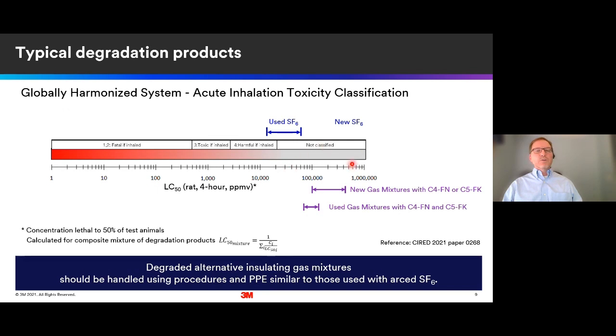Try to put those into perspective. If we look at where those mixtures fall, again, on that GHS, the Globally Harmonized System scale, in this case, it uses the acute inhalation toxicity classification. It's based upon the 4-hour LC50 test in animals, as that's a concentration where lethality is observed in 50% of the test animals. So whereas new SF6 is completely unclassified, once it's been arced in, you can see it moves to a lower classification level, a little bit more hazard. And so as you know, it has to be handled more carefully.